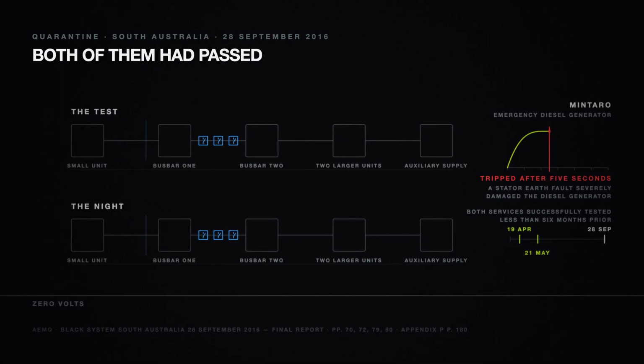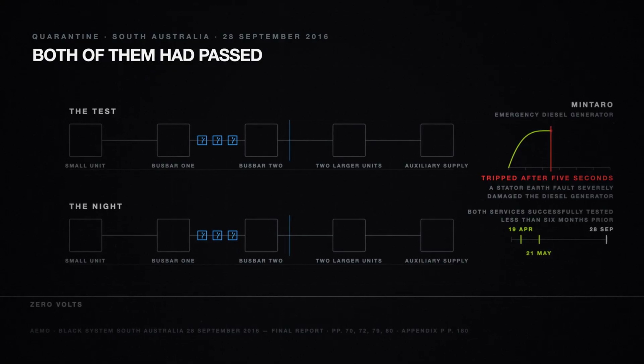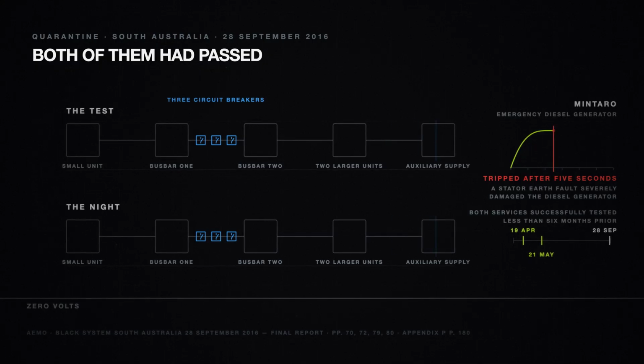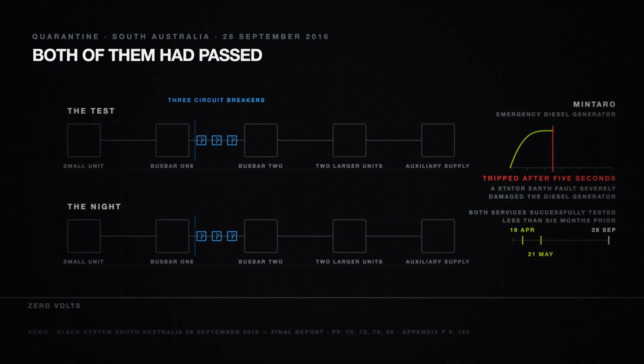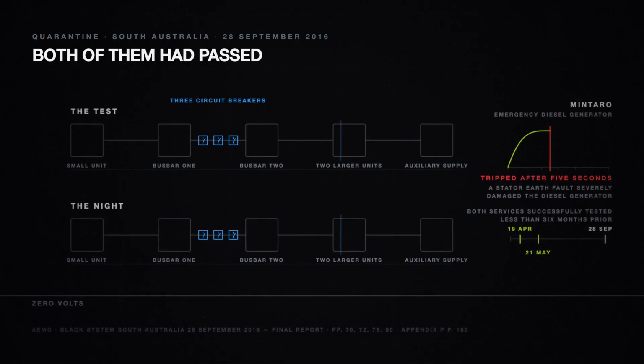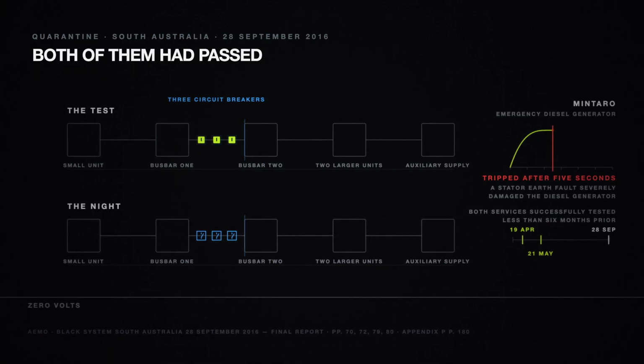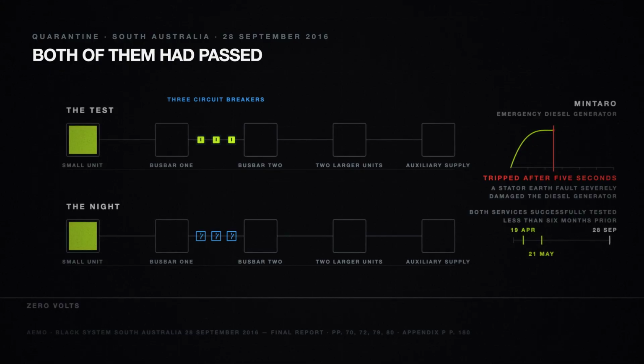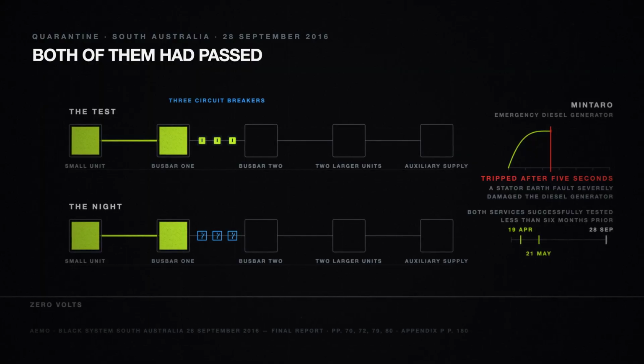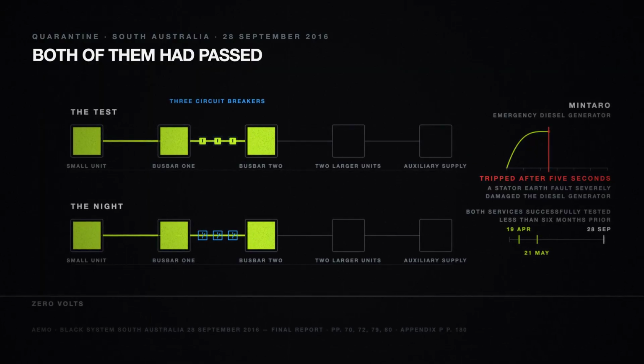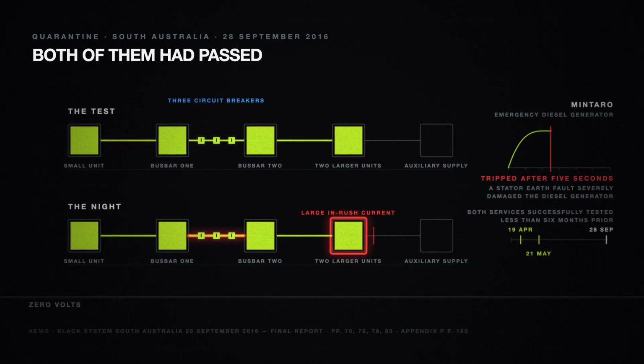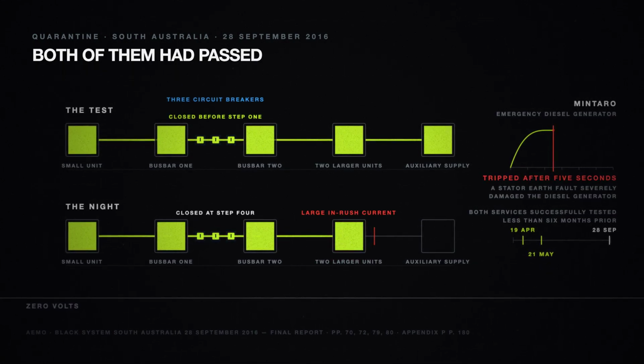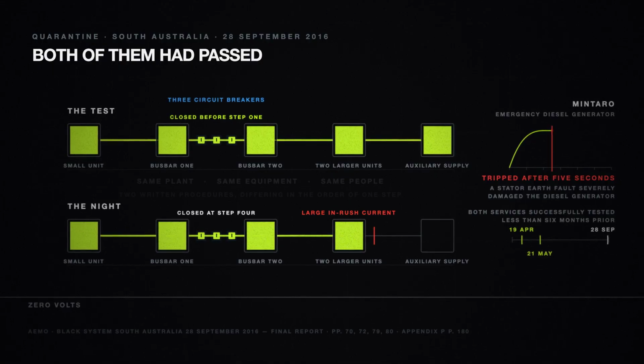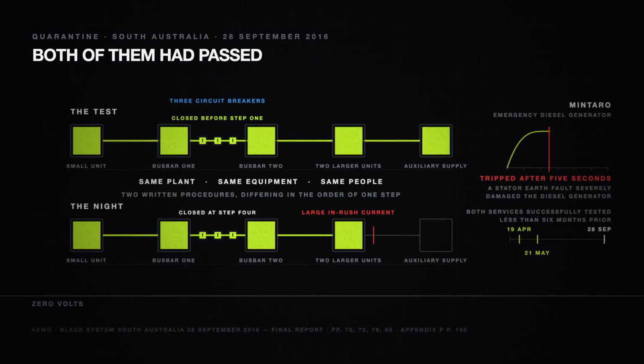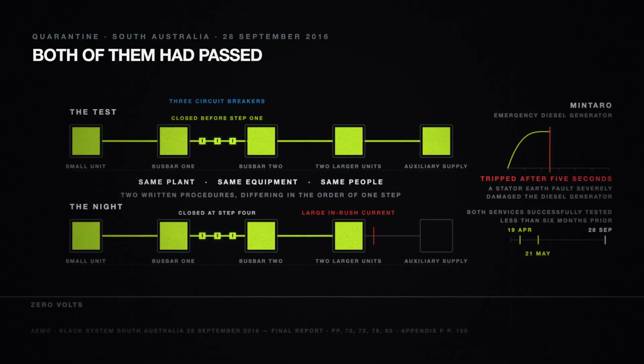At Quarantine, the procedure involves a small generating unit, 2 larger ones, and 3 circuit breakers connecting 2 bus bars. The order those breakers close in is the procedure. In the tests, the 3 breakers were already closed before the small generating unit was started. On the night, the procedure connected the 2 generating units after the smaller was already operating at nominal voltage. Closing them at that point essentially resulted in a large inrush current on the larger unit's transformers. Same plant, same equipment, same people, 2 written procedures differing in the order of 1 step.